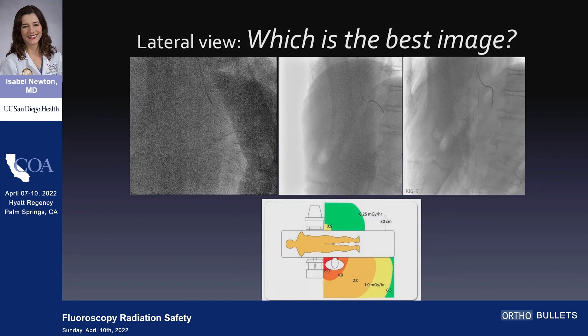This also brings up the point of where to stand. The highest radiation is near the source, so if you are always away from the source, the farthest way you can get from the source, that's going to be the lowest radiation to yourself. For us in IR, when we do a lateral view, I don't care if the lateral view is this way or that way — we see sideways through the patient either way, so I always swing the detector towards myself.